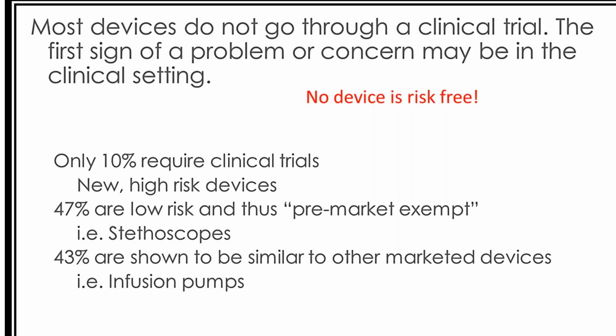So FDA has three categories for medical devices: class 1, class 2, and class 3. These are based on their risk and the regulatory control necessary to provide a reasonable assurance of safety and effectiveness. Class 1 devices generally pose the lowest risk, and class 3 devices pose the highest risk. If you go on the FDA website, you see about 1,700 various product codes. Out of all of those, only 10% require clinical trials. About 90% of them do not need a clinical trial.